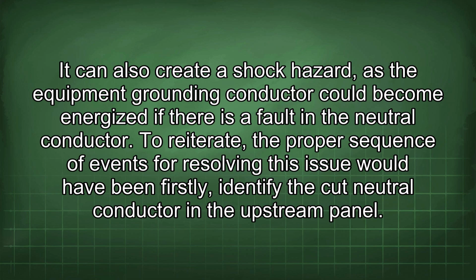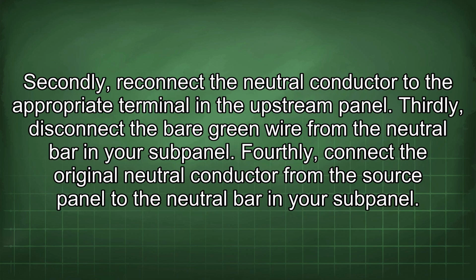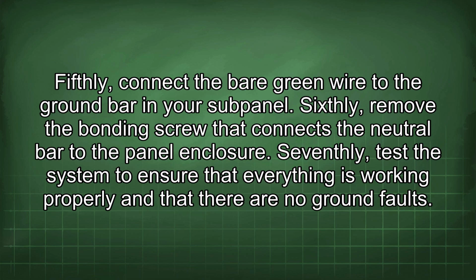To reiterate, the proper sequence of events for resolving this issue would have been: firstly, identify the cut neutral conductor in the upstream panel. Secondly, reconnect the neutral conductor to the appropriate terminal in the upstream panel. Thirdly, disconnect the bare green wire from the neutral bar in your subpanel. Fourthly, connect the original neutral conductor from the source panel to the neutral bar in your subpanel. Fifthly, connect the bare green wire to the ground bar in your subpanel. Sixthly, remove the bonding screw that connects the neutral bar to the panel enclosure. Seventhly, test the system to ensure that everything is working properly and that there are no ground faults.